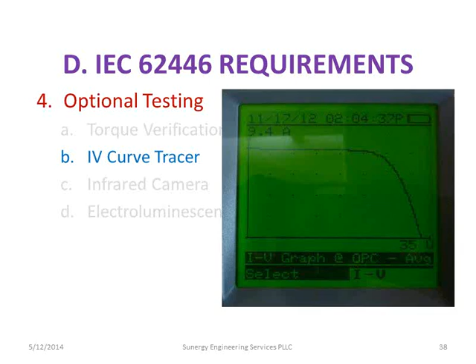And the other thing the curve trace gives you, it'll give you a maximum power point, which is kind of the knee in the curve. So that usually ends up being right around in here. So if you have your ISC and you have your voltage and you've done your performance validation under operation, you've got 3 points of that curve. So you've got most of the curve. And if there's something wrong, you're going to know right away when you do the performance validation. So in my opinion, you don't really need a curve tracer, although if you do have problems, a curve tracer makes them a lot easier to track down. And IEC says curve tracing is optional. It's not required.